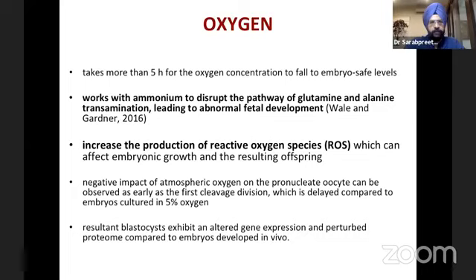It takes more than 5 hours for the oxygen concentration to fall to embryo safe levels. So if you're using a tri-gas incubator, it is better to make dishes and put them in the tri-gas incubator rather than equilibrate the media in a single gas and then transfer them the next morning. You make a dish with media equilibrated in a single gas, put it in the tri-gas, and straight away start your work. That's not the way. You should actually make the dishes in the tri-gas, or else wait for 5 hours and then start using the dishes.